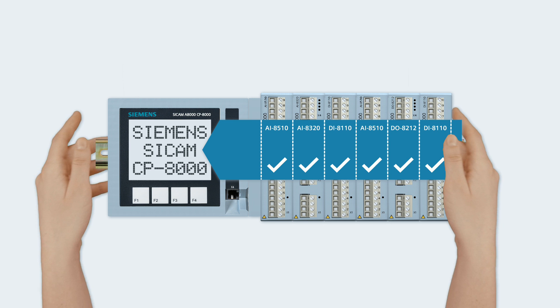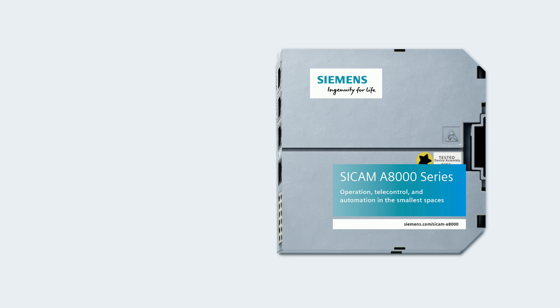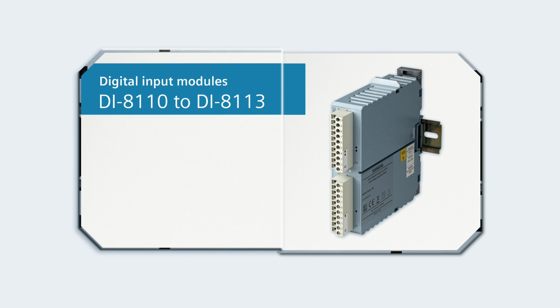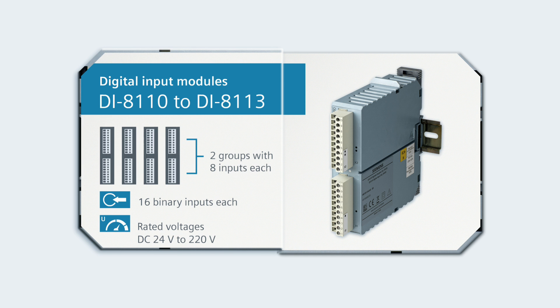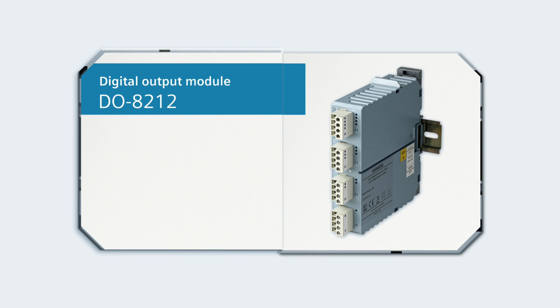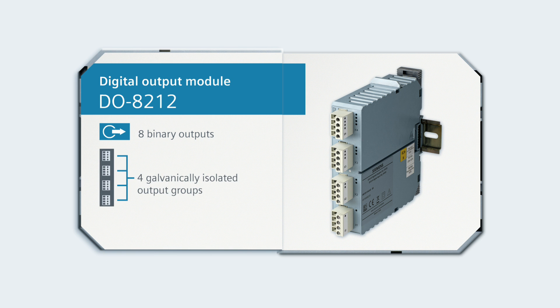The SICAM A8000 series specifically offers four digital modules — DI8110 to DI8113 — with 16 binary inputs each, covering all important rated voltages in the range from 24 to 220 volts. The DO8212 digital module has 8 binary outputs divided into 4 galvanically isolated groups. The output relays handle power up to 150 watts for direct voltages and up to 1250 VA for alternating voltages.